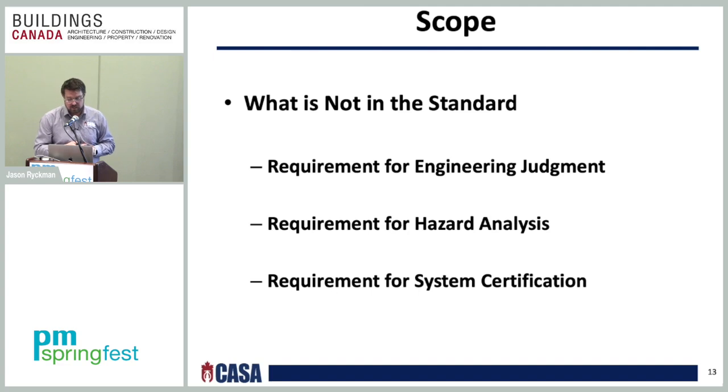The inspection, testing, and maintenance does not certify system designs, okay? So whenever you hear the question, can you certify my system? You can't certify the system. All you can do is make sure that the system is operational, okay? I just wanted to clarify that, make sure everyone's clear with that.